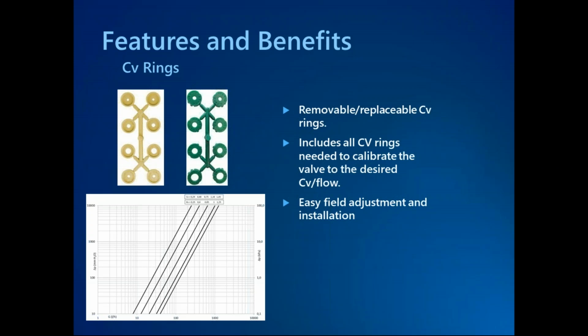If we are going to try to treat the six-way as a modulating control valve to throttle the flow for both heating and cooling, we want to specify and provide a CV for both heating and cooling respectively that is sized for that. You know, the rule of thumb, 10 feet of head pressure drop or 4 psi pressure drop that controls contractors are going to specify. So everybody out there has the ability to do this, whether it's built into the body inherently to the design, or it's some sort of insert ring or insert disc. There is this feature out there. Important to note from a test and balancing standpoint that the valve should have a tag indicating if the CV rings are installed and which ones are installed in which locations. This is going to come back. We'll talk about it a little bit more when it comes to troubleshooting and understanding where pressure drops are located and what readings we're getting, and making sure it all makes sense.